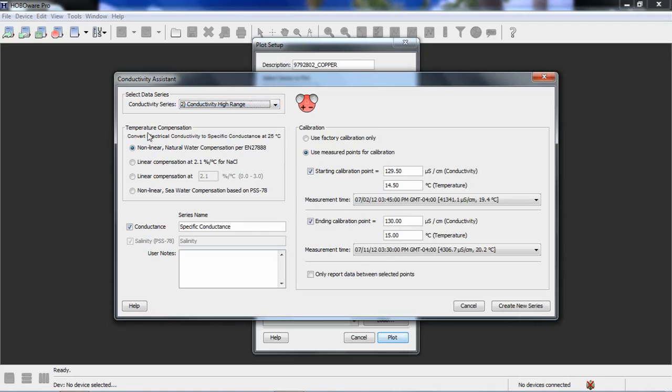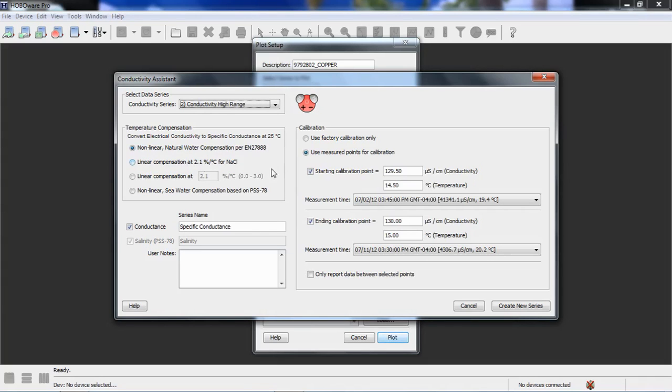We want to select what temperature compensation we want to use. The non-linear natural water compensation is for fresh water. They call that natural water. So, we don't want to use that one. This was a saltwater application. It gives you the ability to put in a linear compensation value, a fixed value for sodium chloride. Or you can put in some other number if you wish. We want to use the non-linear seawater compensation, which is based on PSS 78, which is the practical salinity scale of 1978.